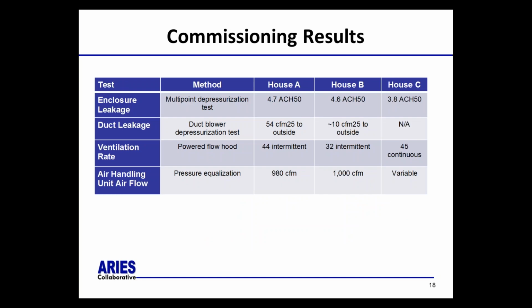So the commissioning results, again, House C has tighter air leakage, less air leakage. It has no duct leakage, of course. And houses A and B have an intermittent ventilation rate, look at the ventilation row, because of the method of ventilation there, between 32 for one house and 44 for the other house. And because it's intermittent, you're not getting ventilation continuously, and we'll see later on how, on average, we're getting ventilation rates that are much lower.